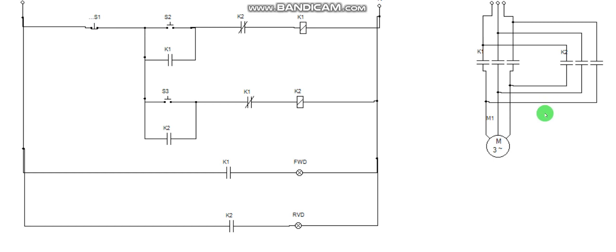It's always a good practice for you to swap at the output side instead of the input side. Both of them, you can also swap the two phases here and do this one the right way. Any of them is okay, but it's always advisable, it's always a very good practice for you to swap at the output side.